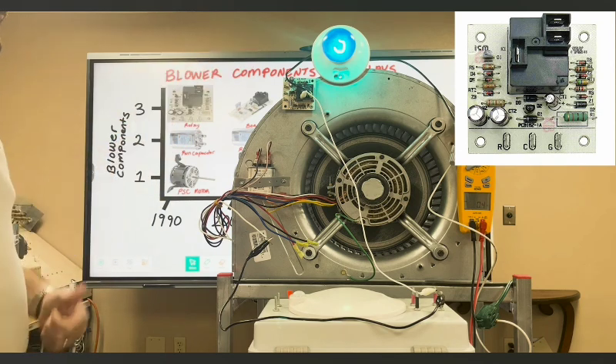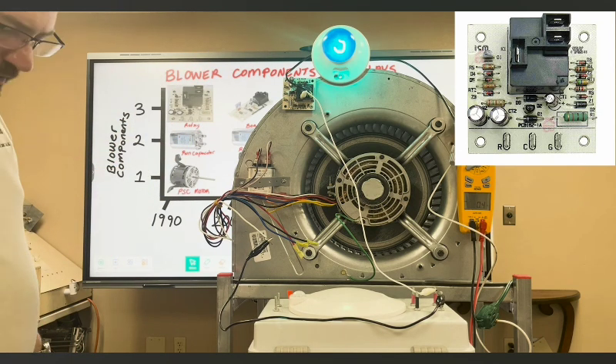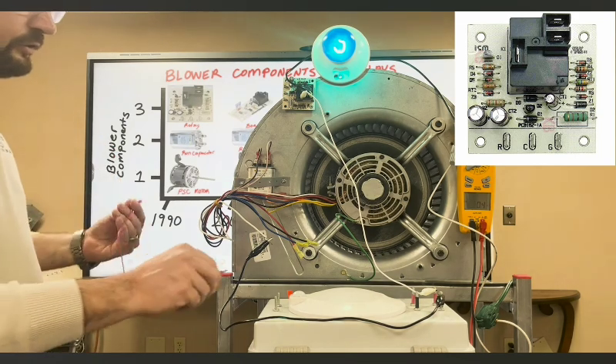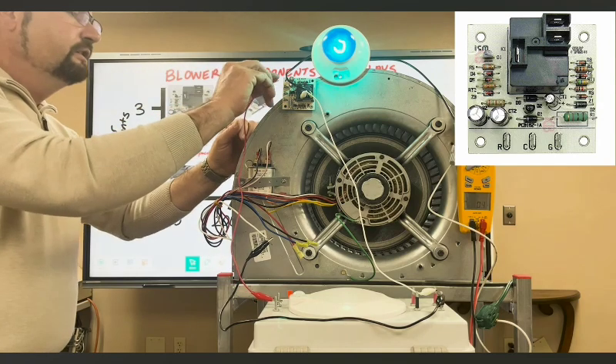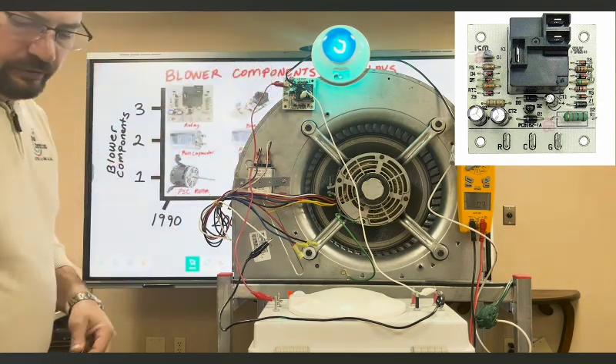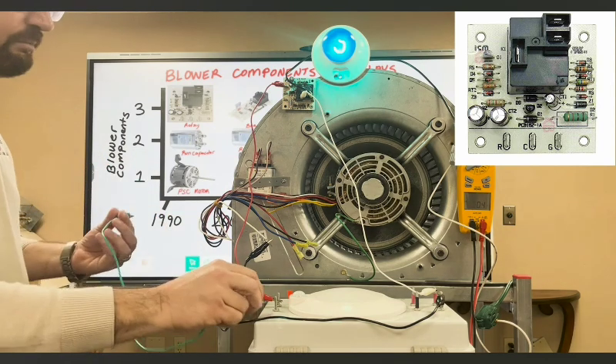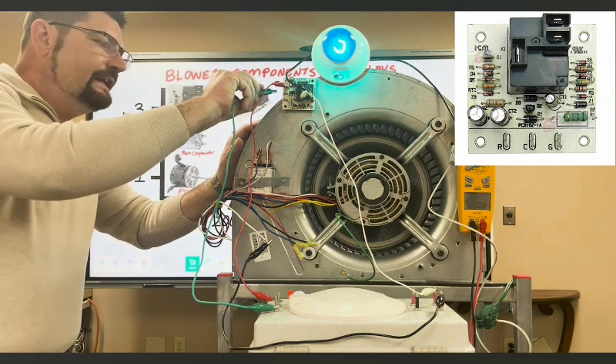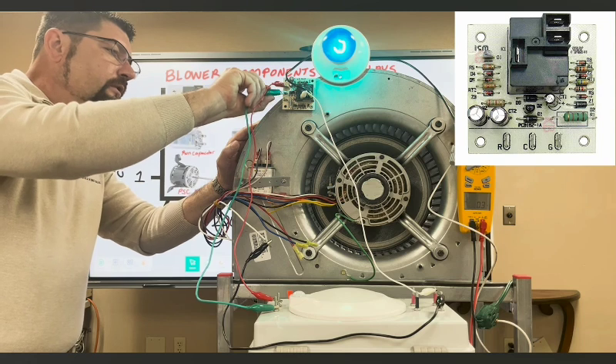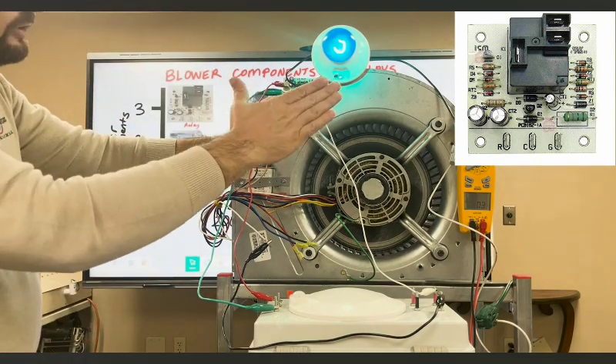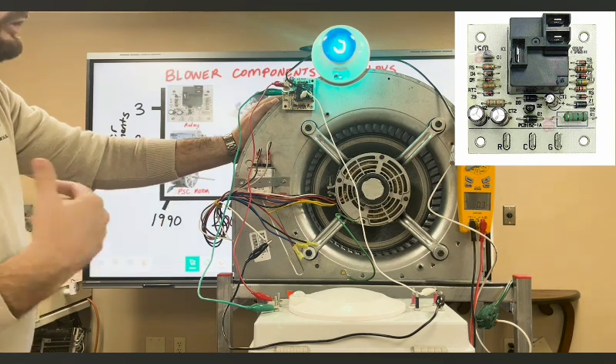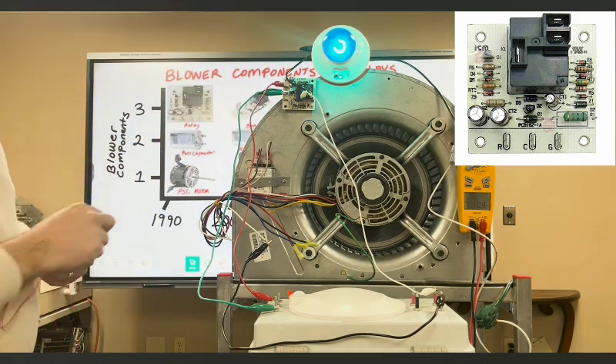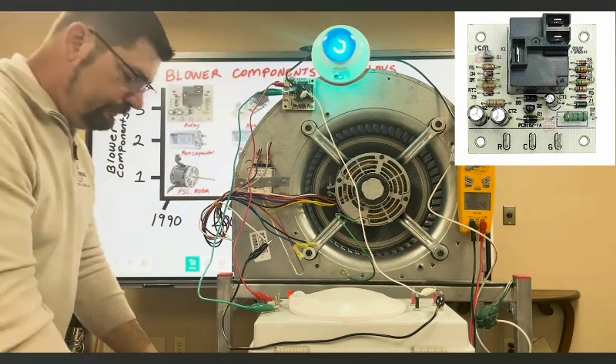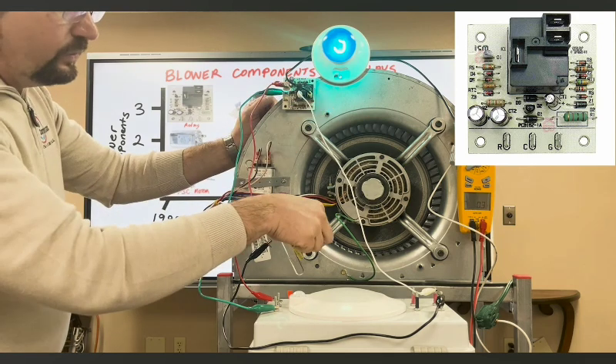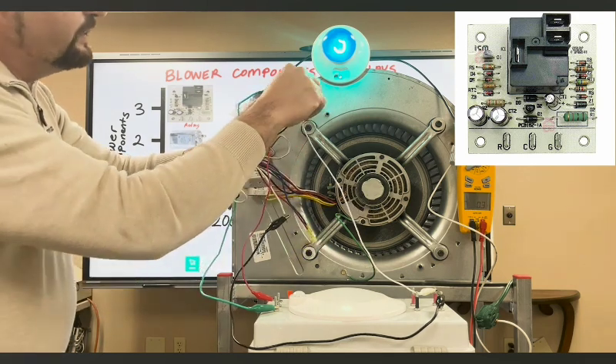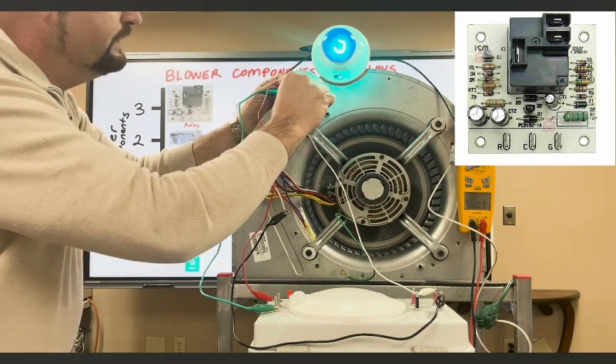We can say maybe this is just standby, there's power. Now the moment that I apply 24 volts to the relay, I will now start having a working low voltage load, even though it's not doing anything just yet, because the board is a load all by itself. So between R and C, it needs to have 24 volts. And there's no change here because we haven't toggled the G terminal. This blower relay is trying to get a G terminal so it can drop out that normally closed and energize the normally open. Before we do that next step, I'm going to take one of these speed taps and wire it up to my relay very carefully here.